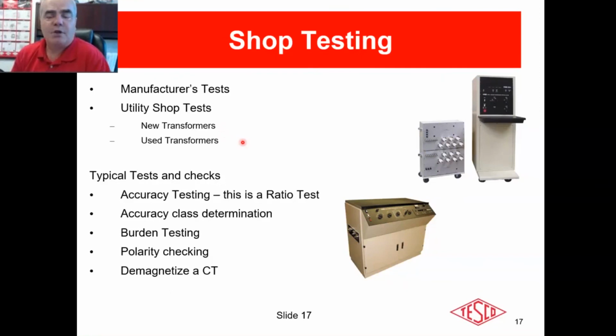Is a 15 or 20-year-old transformer still good? Probably, yeah. There's no moving parts. As long as you haven't overheated it, as long as you haven't put too much current through it, as long as it was manufactured properly, if it's been working for the last 15, good chance it's going to work for at least another 15 and probably longer than that. So if you wanted to reuse a transformer, absolutely check them out in your shop, test them. You can probably put them back out there. There are reasons why you might not, only because there are better transformers available now than there were 20 years ago. And by that, I mean the extended range transformers.